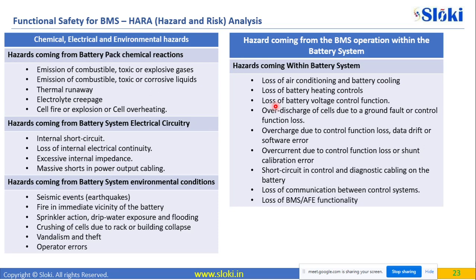It operates only within 15 to 55 degrees centigrade. It doesn't work in negative temperature, and doesn't work well beyond 55-60 degrees; it can even explode. So battery cooling is really important. How do you achieve that? If it's an air-cooled system, what if the fan goes bad and air cooling isn't happening? What if it's oil-cooled, water-cooled, or an active cooling system, and the pump or coolant circulation isn't really happening? How do you detect that? Do you give highest priority to this cooling system, the thermal management? All of this becomes a crucial part.